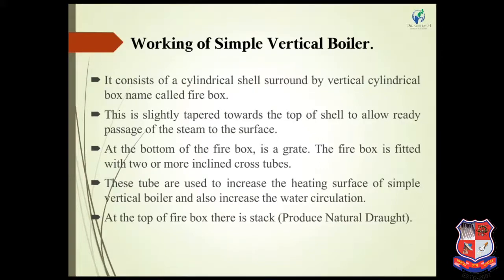At the top of the firebox is a stack, meaning the firebox has a cylindrical shape and is completely vertical to the atmosphere, which creates a natural draft. This means higher temperature, low density flue gases come out from the chimney, and primary air of higher density enters into the firebox. That's called a natural draft.